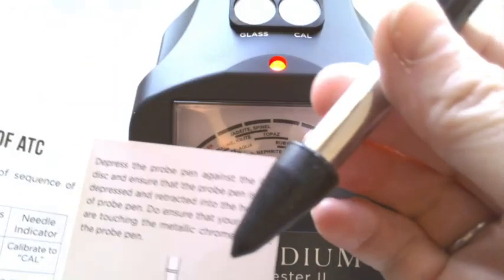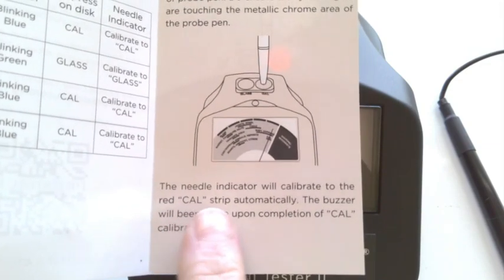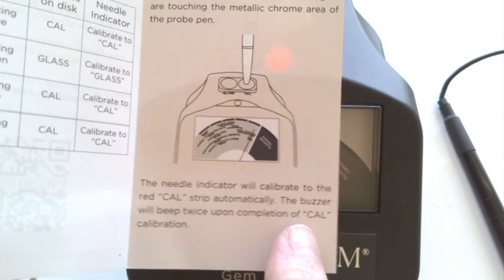So once we have the blue blinking light, it says that we need to make sure that our fingers are touching the pen on the metal. We need to press down. The needle indicator will calibrate to the red Cal strip automatically. The buzzer will beep twice upon completion of calibration.